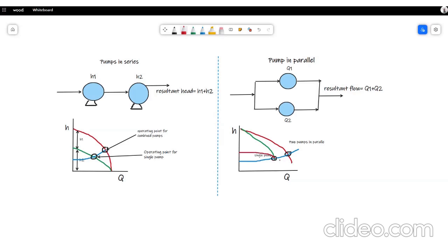So what will happen then in parallel operation, due to not having the steepness, the combined effect of both will lead the pumps to operate in the minimum continuous flow region.